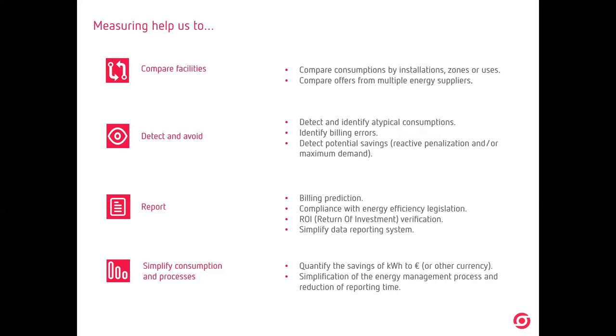It happened, for example, in Circutor. We started measuring and we saw that during the weekend we had consumption and we are not working during weekends. And it was because the people who clean Circutor connect the aircon in summer or connect the heating system in winter, and they left it connected during the weekend. Well, after measuring, we checked that it happens, and with the software we created a system in order to avoid that. If we see higher consumption during weekends, we create a calendar, and we disconnect the loads. We disconnect the lines if there is no one in the office, okay?